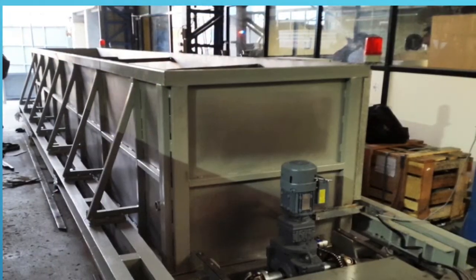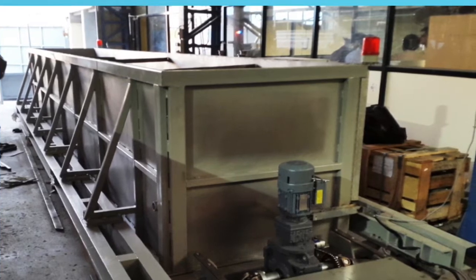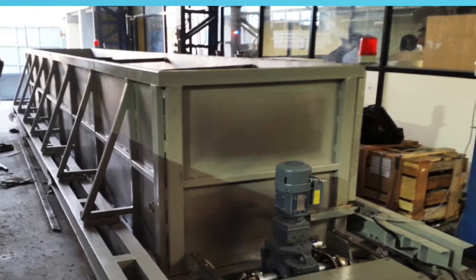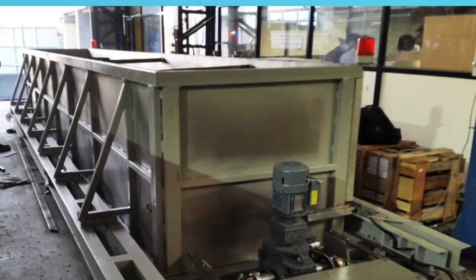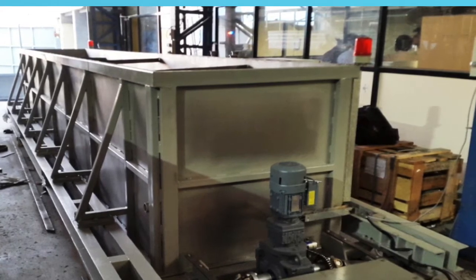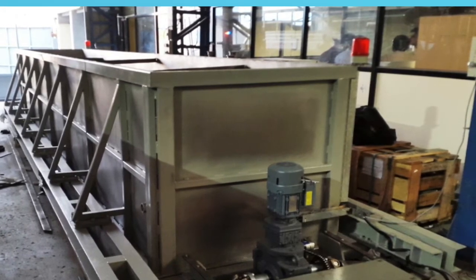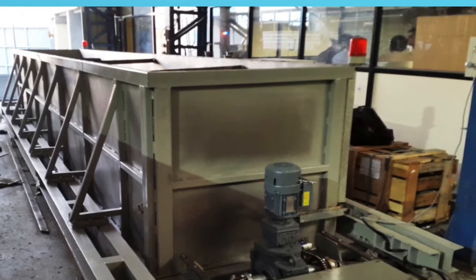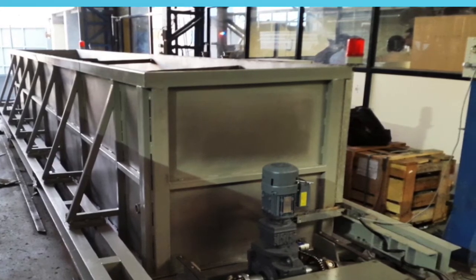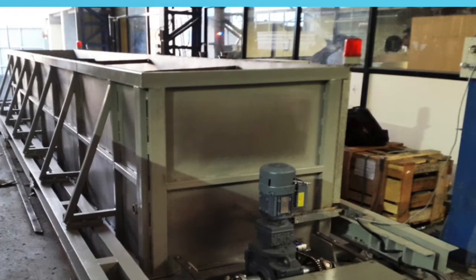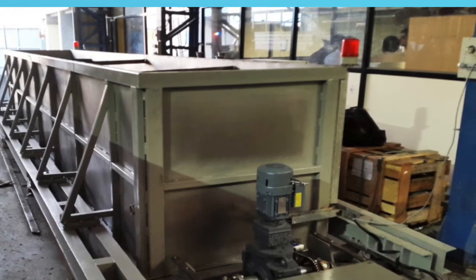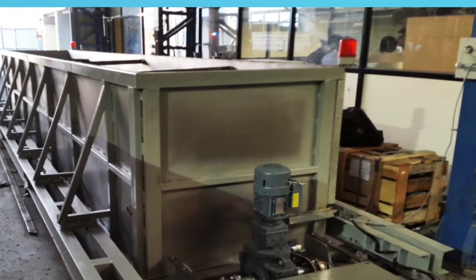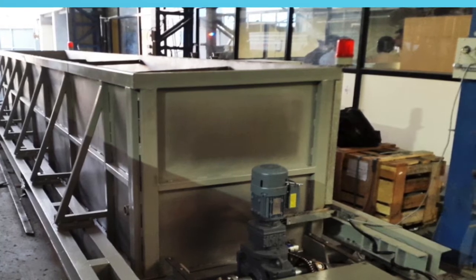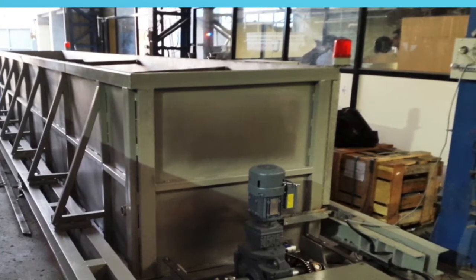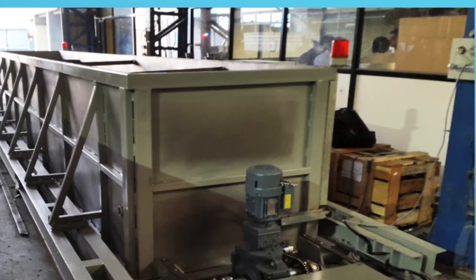This is a typical SS tank of size 7500 x 1200 x 1250 mm with 12 metric ton capacity, used for water-deep ultrasonic testing of aircraft parts. The total tank moves on rails with SEW drive and VFD. Positional accuracy is achieved by an absolute type encoder, and it is programmed through Siemens PLC for performing a designated sequence.